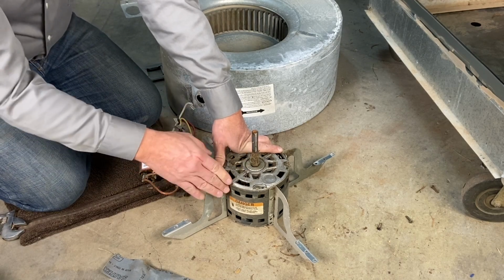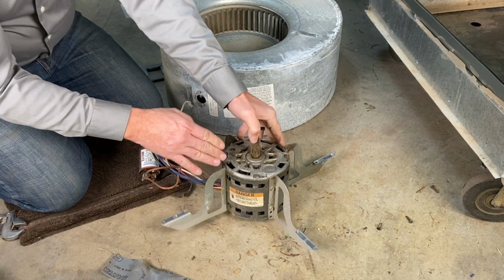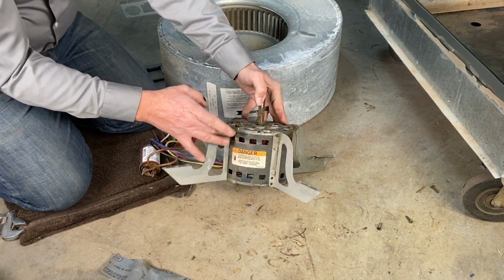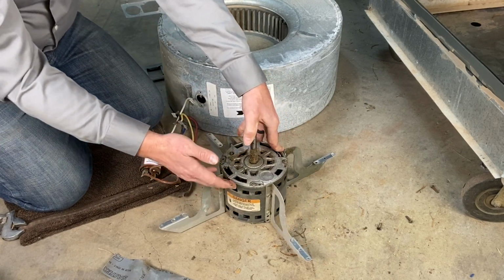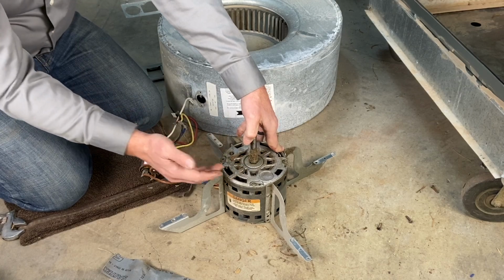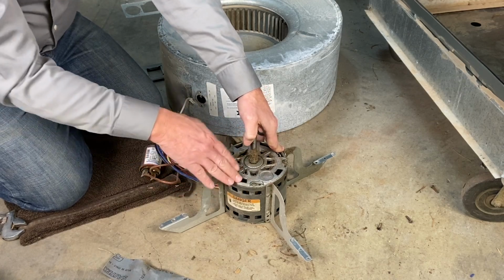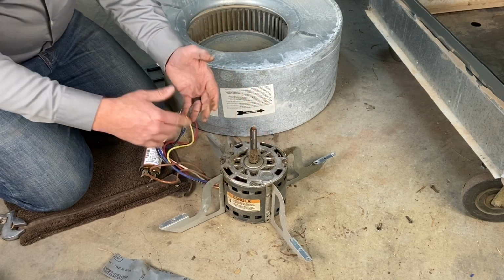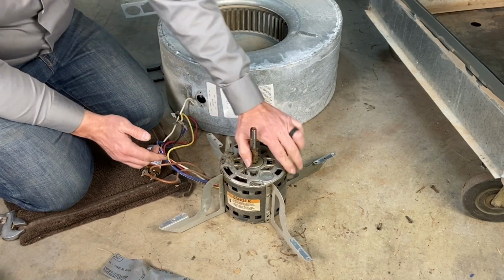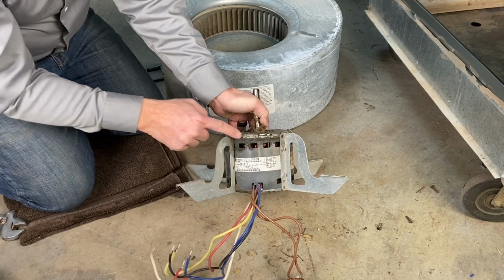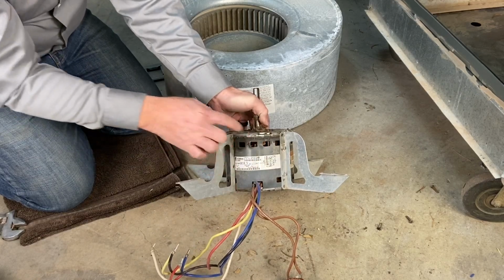So what I want to do is note that in the service invoice. I want to note that the motor does show signs of leaking. Now this could simply be the last guy put oil in to pull it and clean it and it's leaking out. But either way, I want to note that so it doesn't come back on me. We did let the customer know that this motor is starting to show signs of wear. And again, here you can see this as well, this discoloration from the oil.